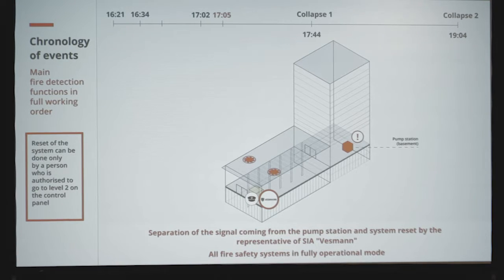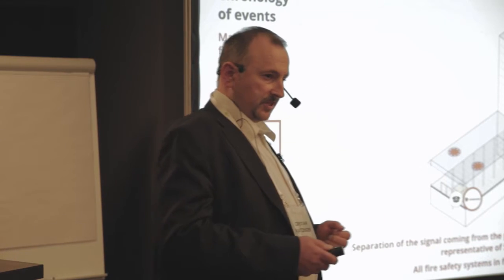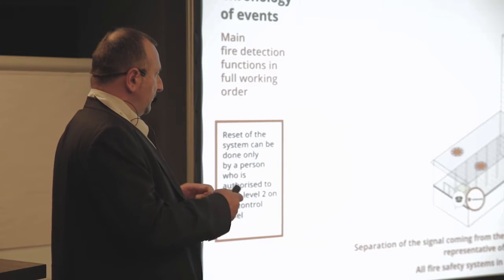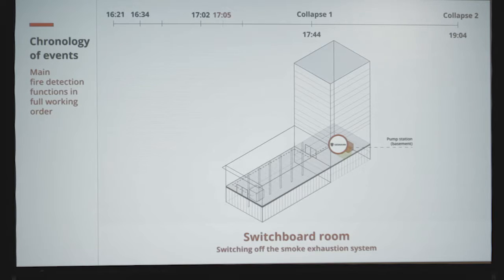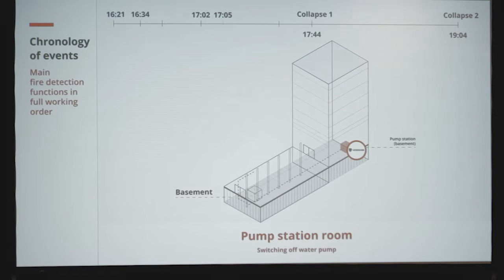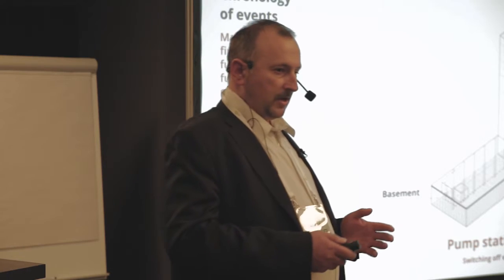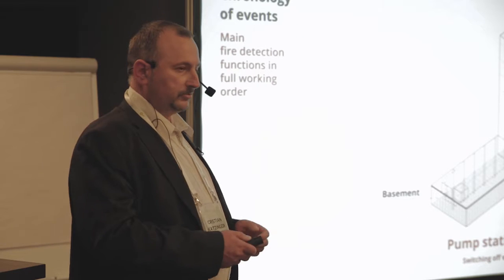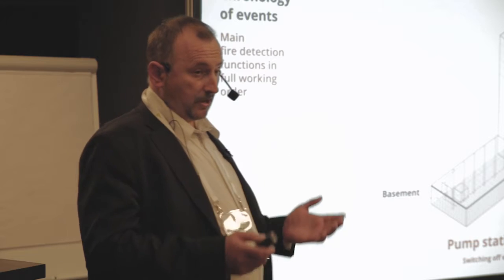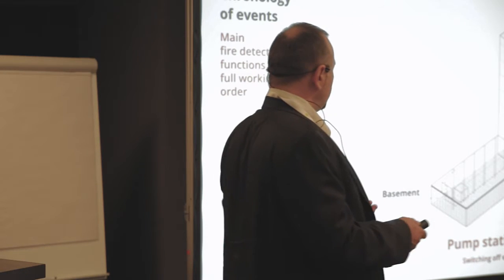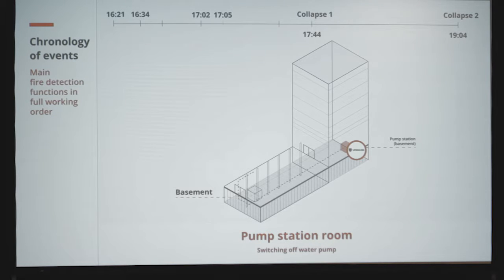First he separated the signals coming from the pump station, so he could reset the control unit in standby mode. And afterwards, he went to the switchboard room. He put off the smoke exhaustion system. Then he went to the server room. He reset the automatic voice alarm system. And last but not least, he went to the pump station. Of course, when he came to the underground, from the pump station, outside, there's a loud sprinkler bell ringing. He heard it. He went into the pump station, and he switched off the water pump.